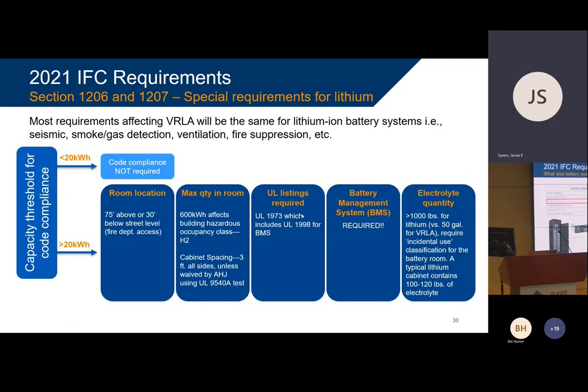So let's see what that involves. What's different for lithium than it is for lead acid? And I'm going to pretty much call questions by the end of this slide. Just wanted to hit the high points here. First of all, if you're less than 20 kilowatt hours for some reason, you have a small lithium cabinet, you're not required to comply with the code at all. But the vast majority of lithium cabinets for UPSs are greater than 20 kilowatt hours.